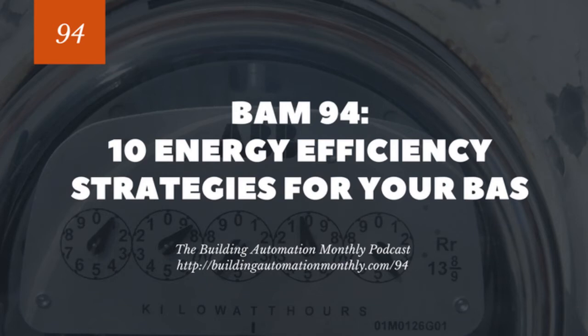I'm a firm believer of not filter DP sensors, but at least filter switches, where you're using something like an AFS 465, I believe it is. That's the airflow pressure sensor with automatic reset. And basically you set that to whatever your pressure drop is based on your filter type. And when it goes below that, when your pressure drop is getting to the point where it means you've got a dirty filter, then you're able to see that and you're able to go and fix those filters.